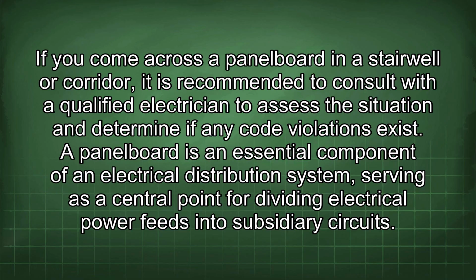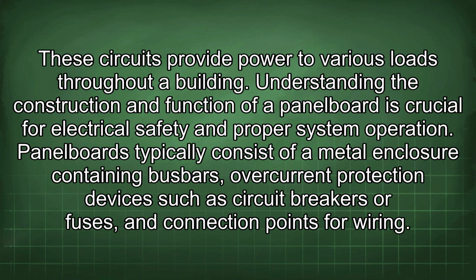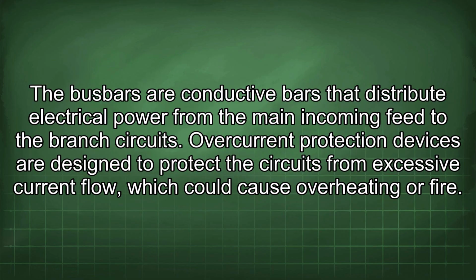A panelboard is an essential component of an electrical distribution system, serving as a central point for dividing electrical power feeds into subsidiary circuits. These circuits provide power to various loads throughout a building. Understanding the construction and function of a panelboard is crucial for electrical safety and proper system operation. Panelboards typically consist of a metal enclosure containing busbars, overcurrent protection devices such as circuit breakers or fuses, and connection points for wiring. The busbars are conductive bars that distribute electrical power from the main incoming feed to the branch circuits. Overcurrent protection devices are designed to protect the circuits from excessive current flow, which could cause overheating or fire.